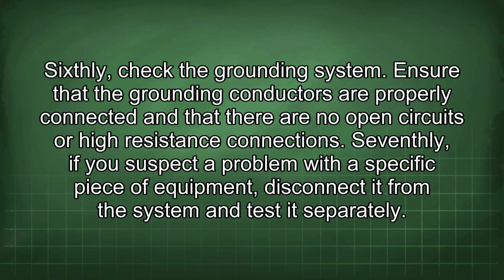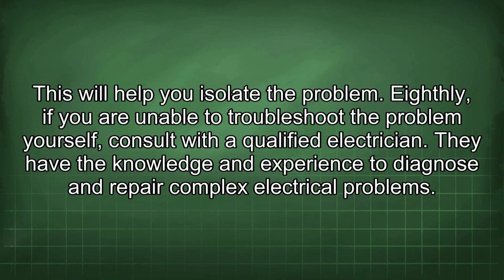Sixthly, check the grounding system. Ensure that the grounding conductors are properly connected and that there are no open circuits or high resistance connections. Seventhly, if you suspect a problem with a specific piece of equipment, disconnect it from the system and test it separately. This will help you isolate the problem. Eighthly, if you are unable to troubleshoot the problem yourself, consult with a qualified electrician. They have the knowledge and experience to diagnose and repair complex electrical problems.